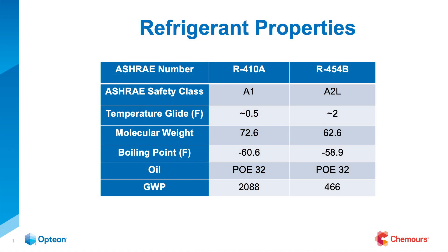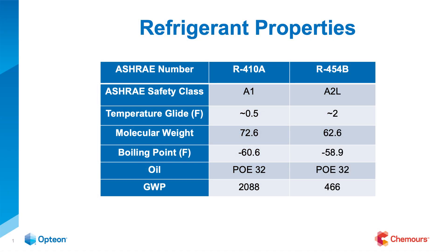If we put some of the properties that are always of interest when comparing refrigerants up here, you can see some are very similar with some changes. Things like molecular weight, boiling point, materials compatibility, lubricant recommendations, and temperature glide are all going to be very similar in handling and performance. The cases where you'd need to do anything drastically different from 410A are going to be minimal.